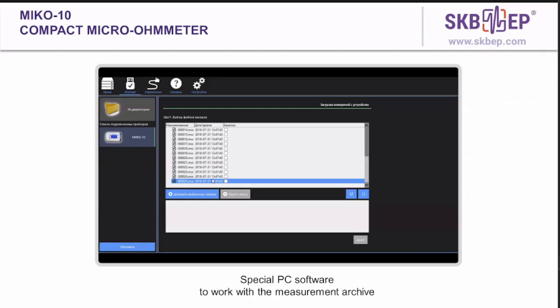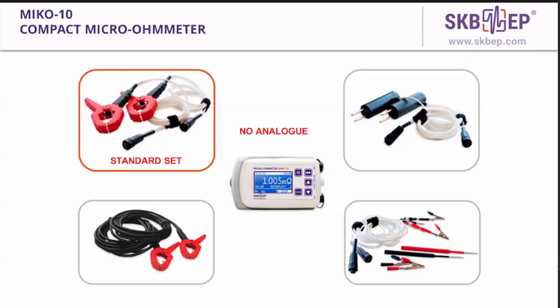The instrument has an energy-independent memory of up to 100 recordings. All the recordings are automatically saved. Then we can transfer the recordings to the PC and use special software to work with the measurement archive. Here are the test cables that come with the standard complete set, indicated in the red line in the left top corner. All the rest come with the additional accessory set.